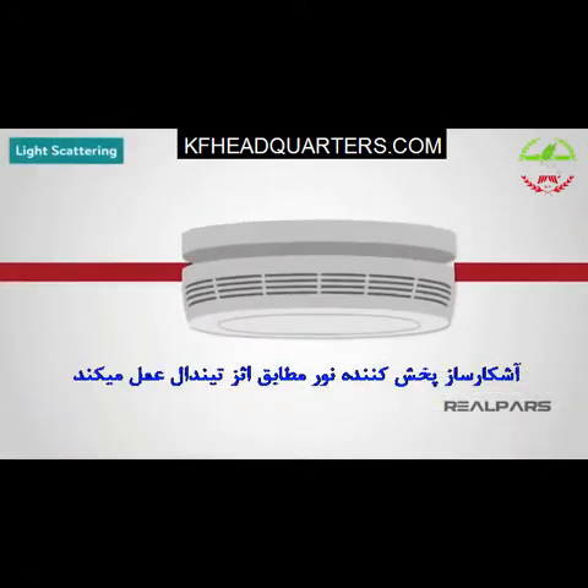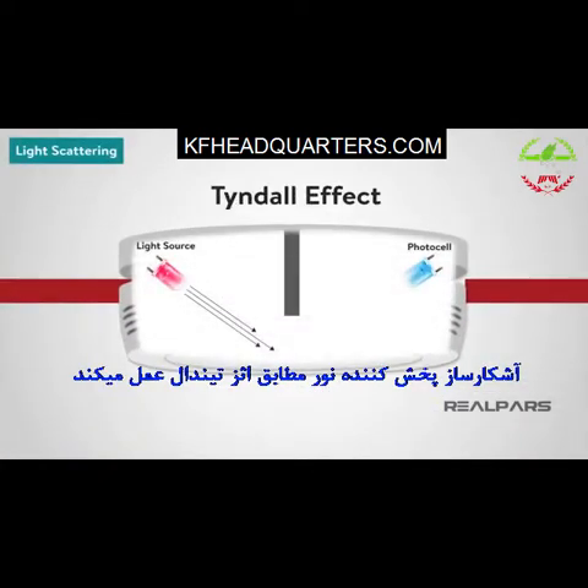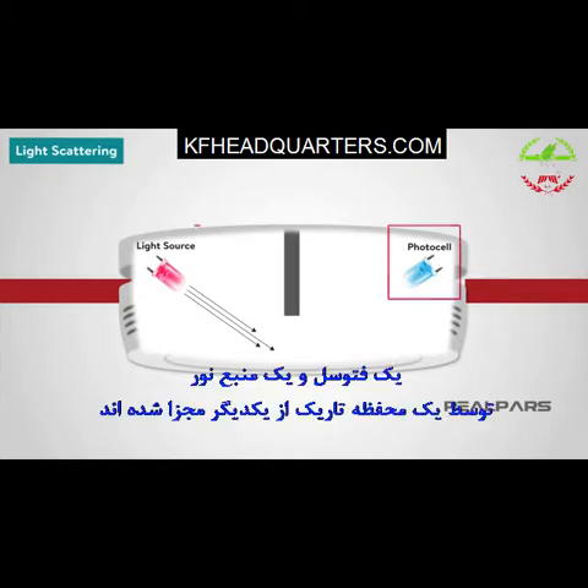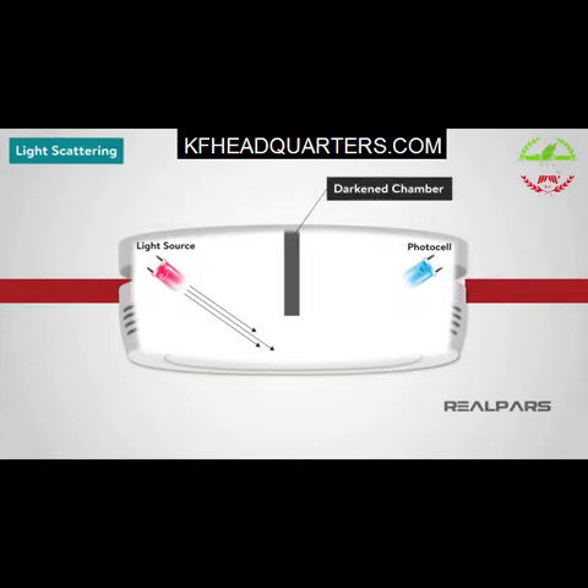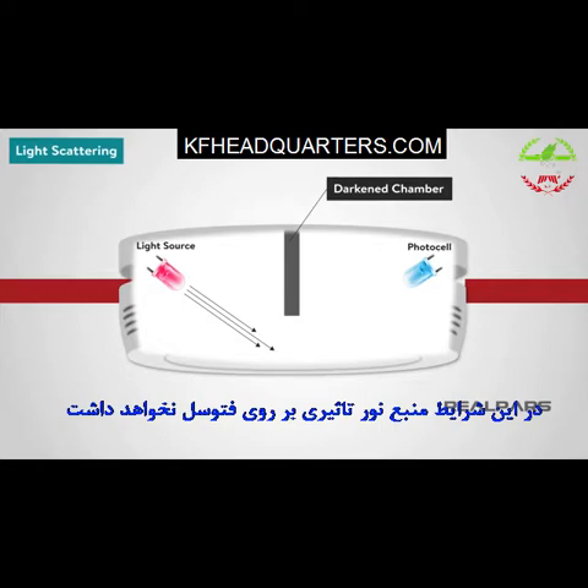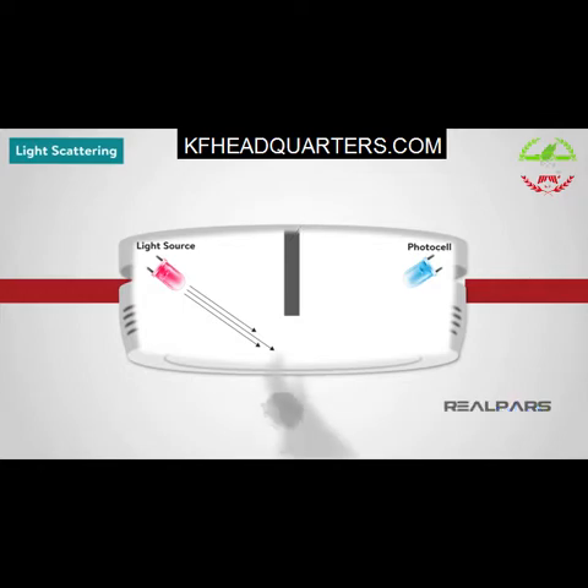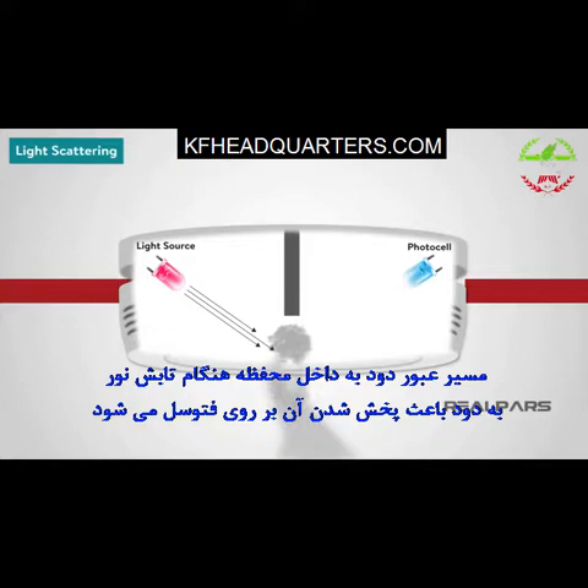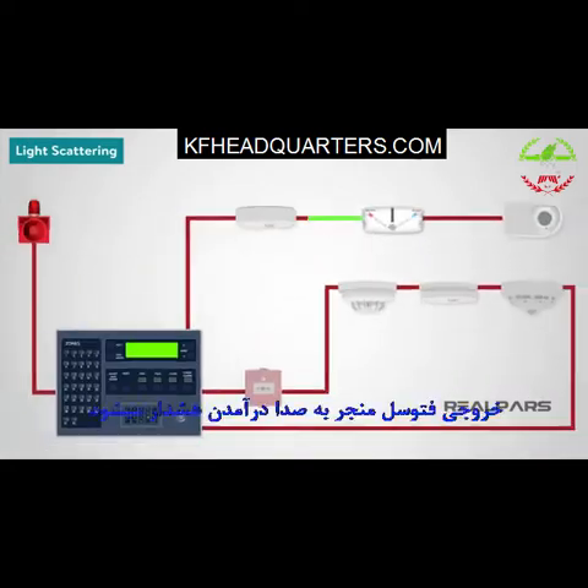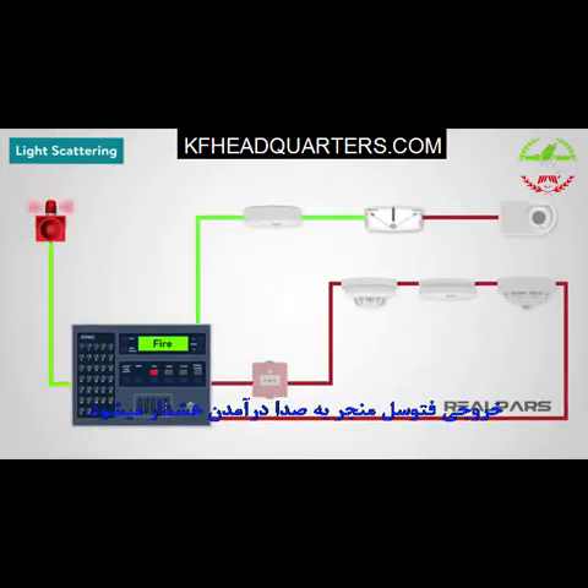The light scattering smoke detector operates on the Tyndall effect. A photocell and light source are separated from each other by a darkened chamber, such that the light source does not fall on the photocell. The passage of smoke into the chamber causes the light from the source to be scattered and fall on the photocell. The photocell output is then used to initiate an alarm.